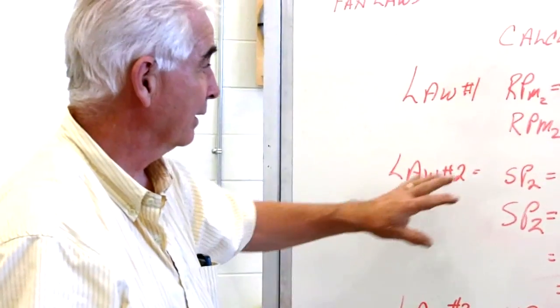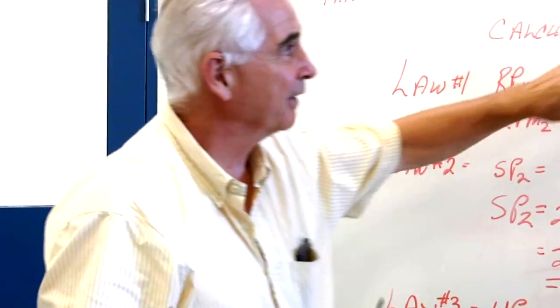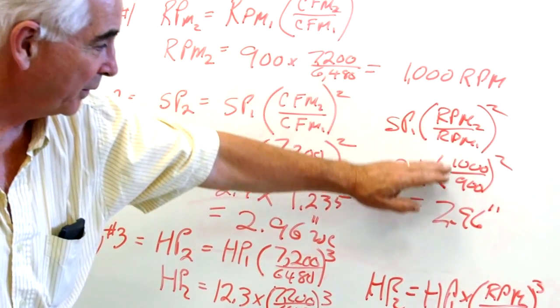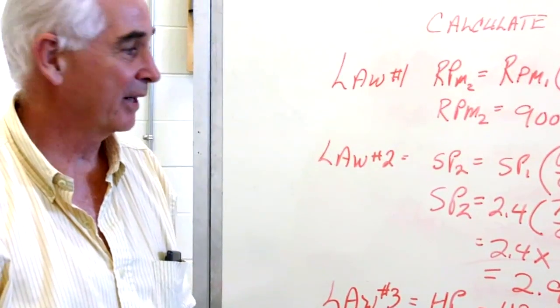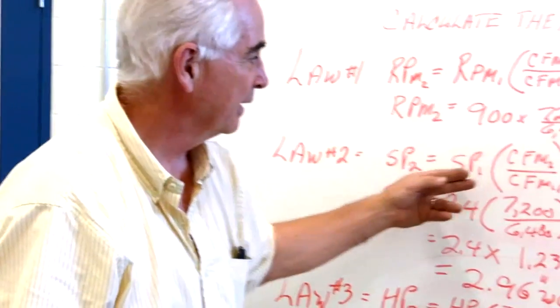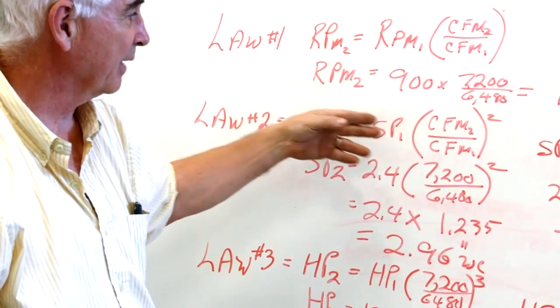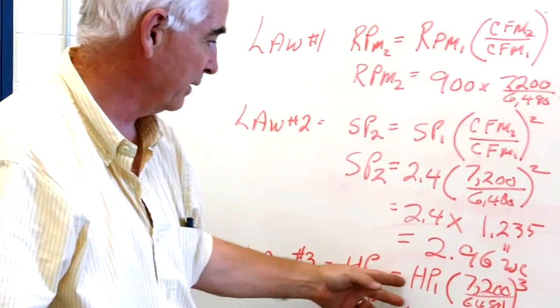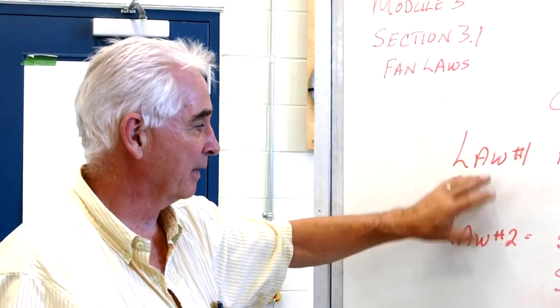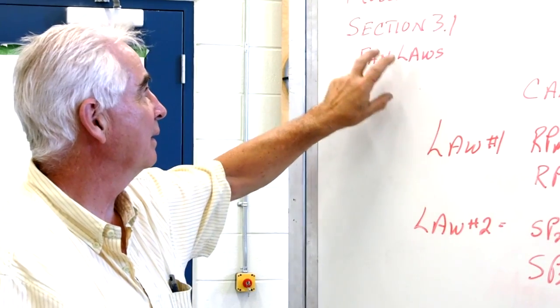Both are correct, but personally I stay with whichever ratio I started with — CFM or RPM — to avoid carrying forward a calculation error. Since RPM varies directly as CFM, you can use either ratio for Laws 2 and 3. That's a quick explanation of Fan Laws 1, 2, and 3. You'll see more in Section 3.1 of Module 3. I always draw a little picture — it helps.